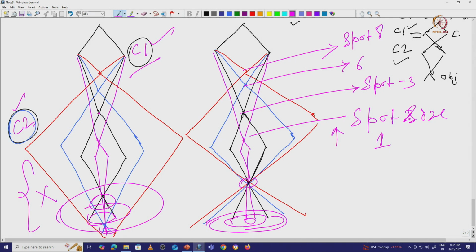So, you can see whenever we go from a very low spot size to a high spot size, due to the very strong magnetic field, the crossover point goes up, and the beam is spread too much in this region when it goes through the C2 lens. Our C2 lens is somewhere here, right?